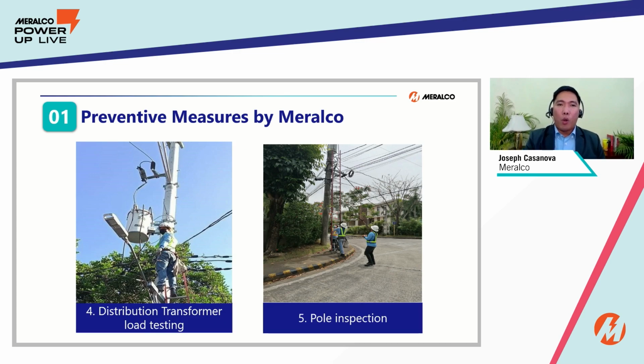Next. So Meralco also conducts distribution transformer load testing. So which basically checks whether the distribution transformer serving our customer is still within efficient loading. So normally around 80% loading po tayo dito. So once overloading is found, we will have to correct this by reviewing the accounts and the contracted capacity connected to that transformer. So we will then collaborate with you or the affected customers for need to upgrade if necessary. So para na din po ito sa kaligtasan ninyo, kaligtasan ng facilities natin, at sa further na pag-improve pa ng ating power quality.